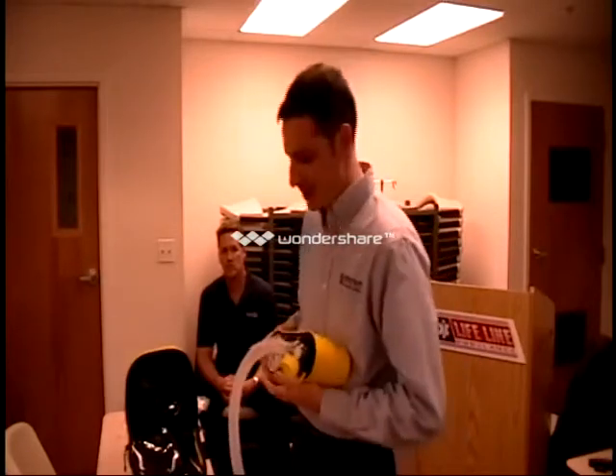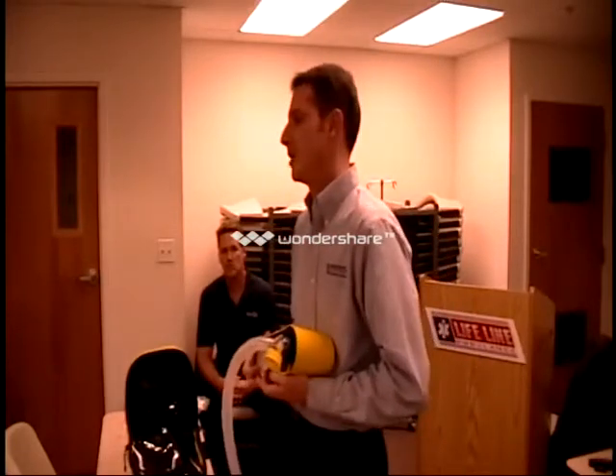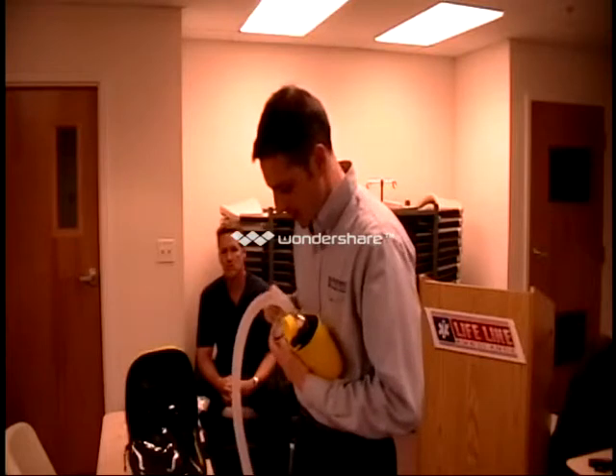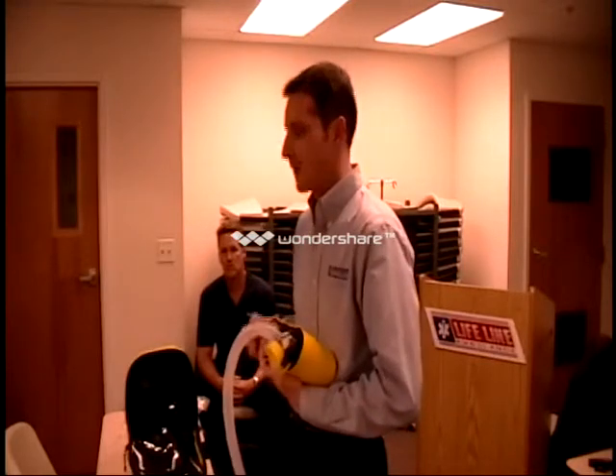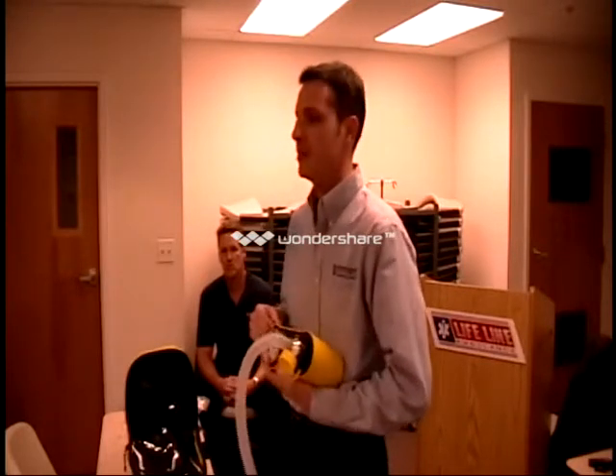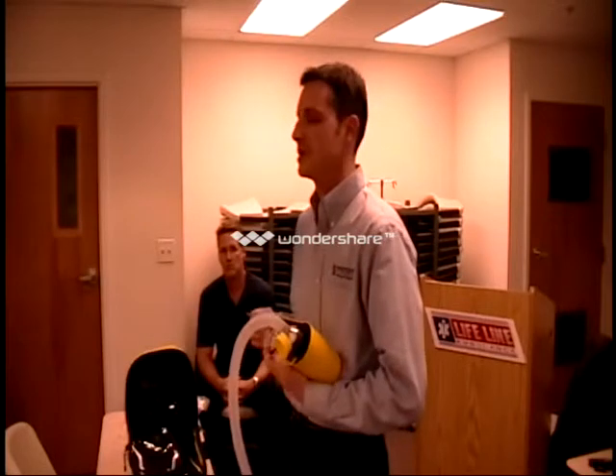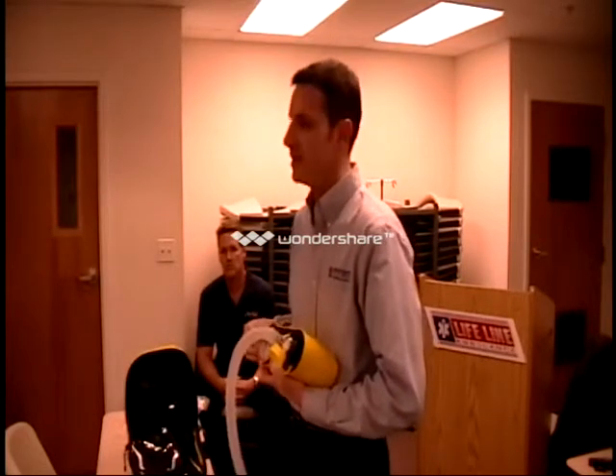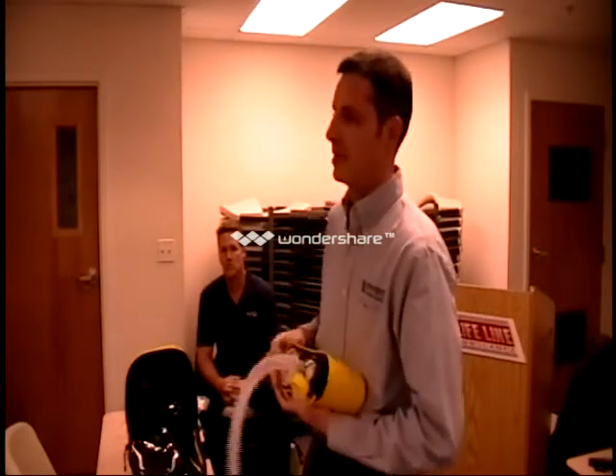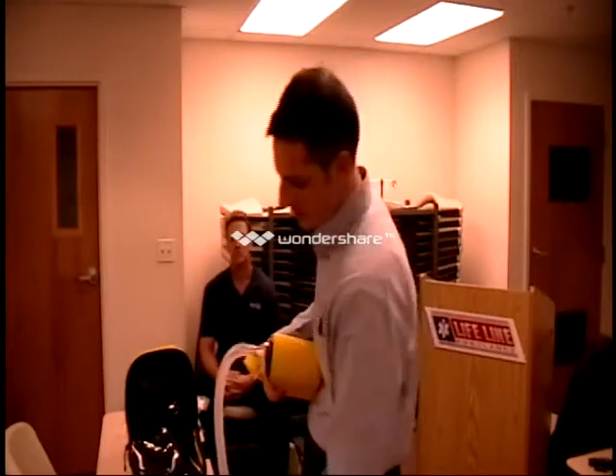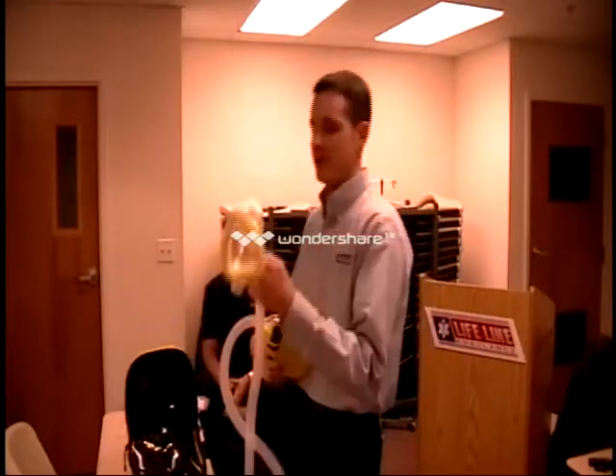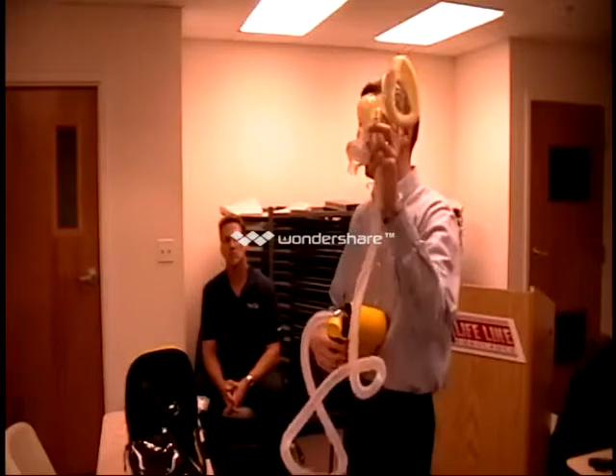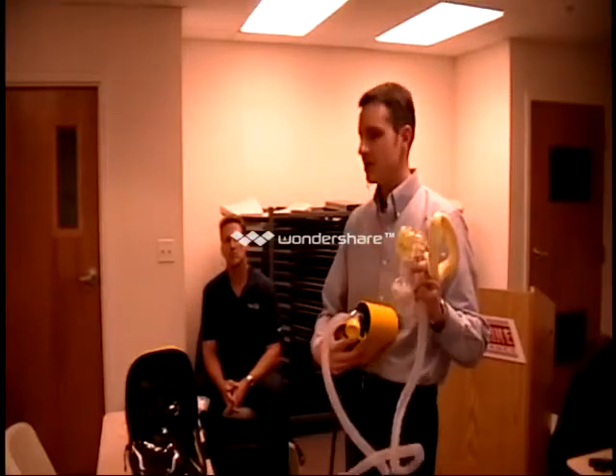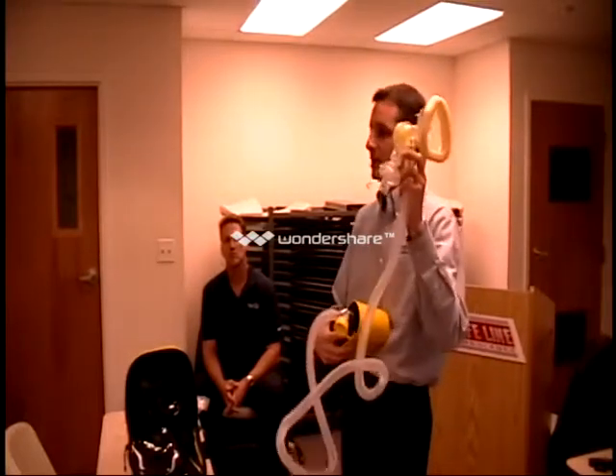Everything in the world of CPAP is measured in centimeters of water pressure. This gauge here goes 0 to 20. For all intents and purposes, you just need to make sure you're staying in the green, which is 0 to 10. Where that needle sits on exhalation is the CPAP pressure the patient's getting. And the reason the needle's going to fluctuate is because this manometer is being driven by a sensor port right here in the mask. It's not what the system said, it's the airway pressure the patient's actually getting.